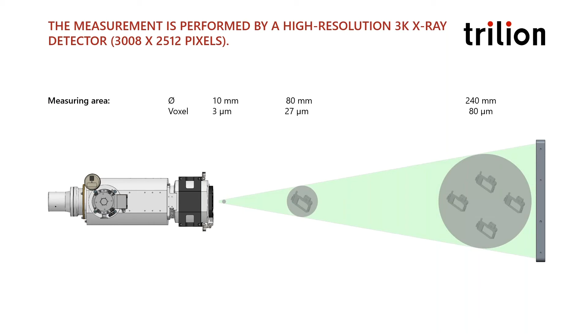But this part that we're looking at here, for example, you can get the best resolution at a 27 micron voxel size. But if you can sacrifice resolution, you can do batch scanning in the larger measuring volumes and get up to, I've seen anywhere from 5 parts all the way up to 300 small parts being measured at once. So whenever you look at this economy of scale, you can get scan times down to 3 seconds per part, which is incredible in a high throughput situation.